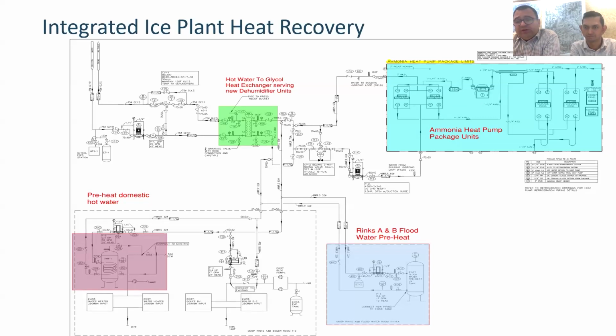So when the heat pump has run hours but there's no demand, we can use the building loop as a heat sink and basically inject the heat into the building piping in the hydronic system, in which basically we can store it there.